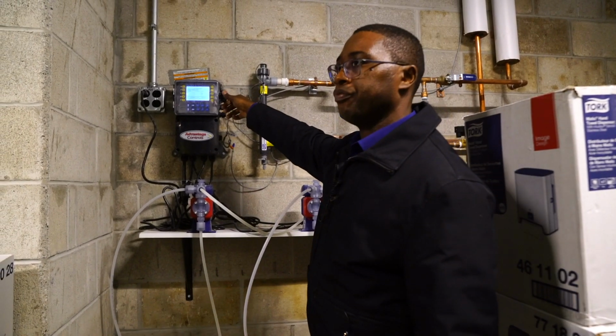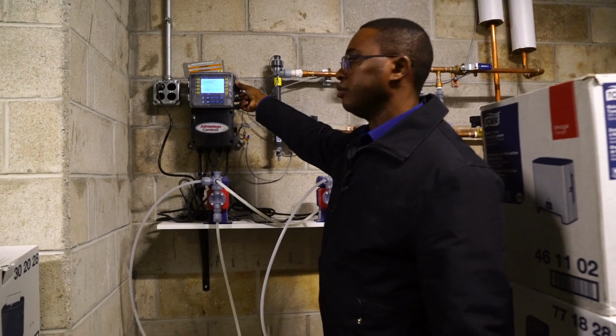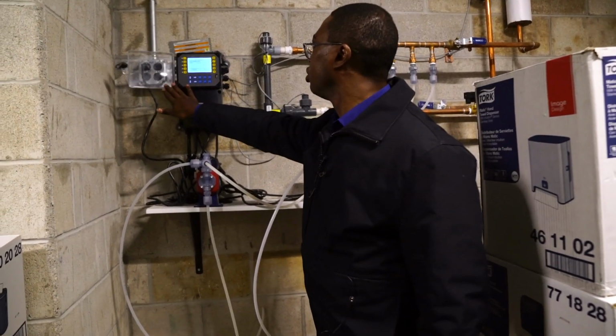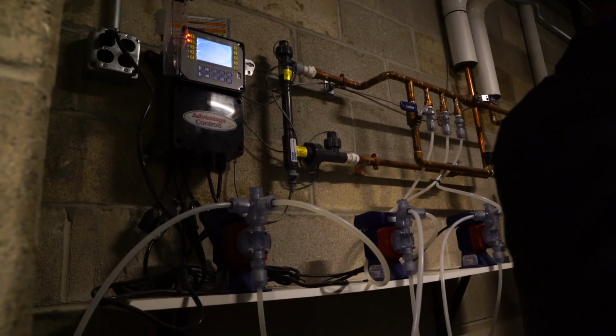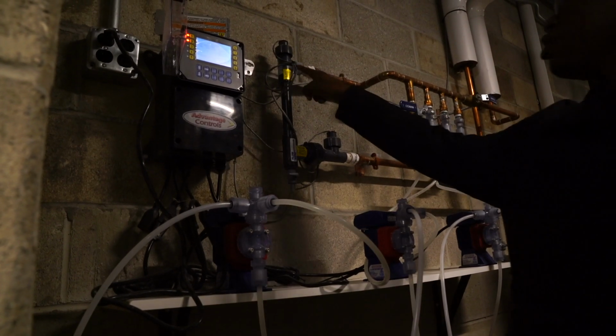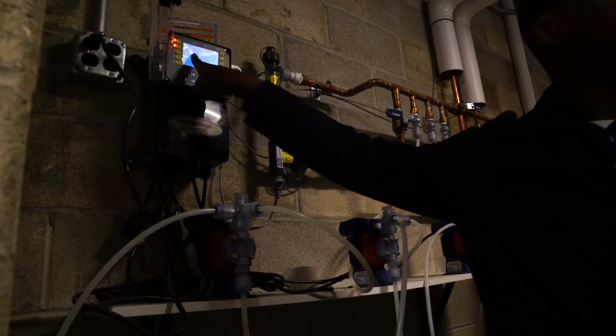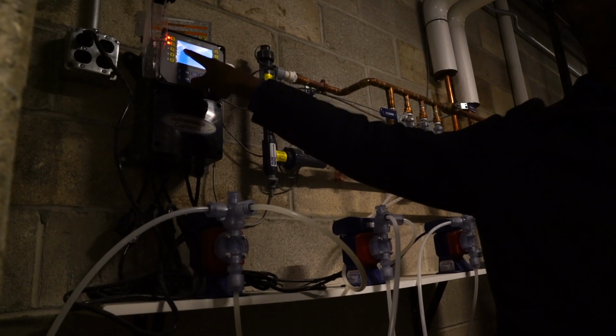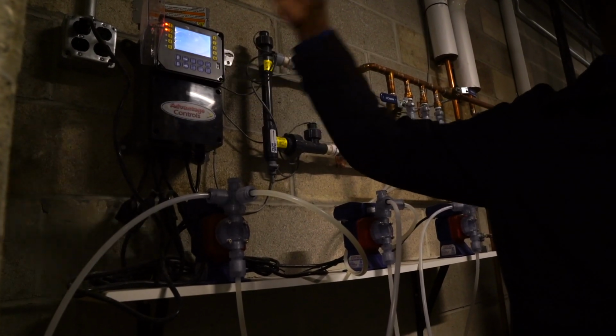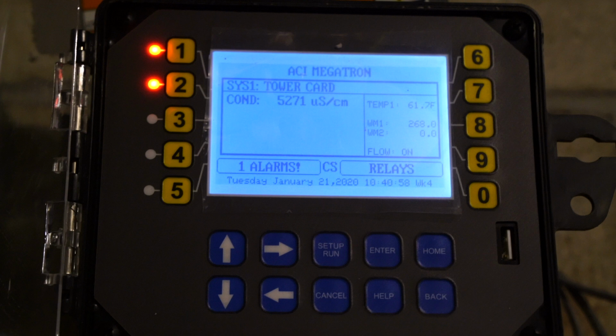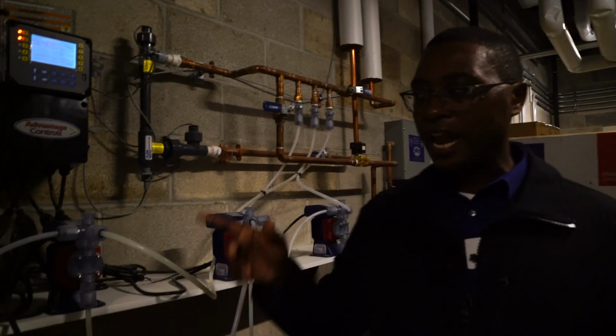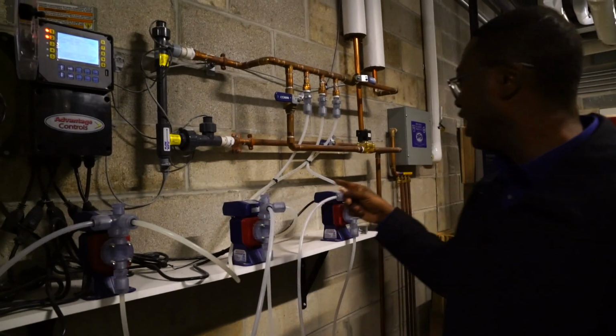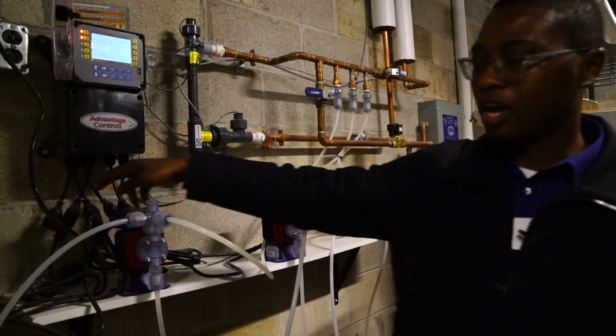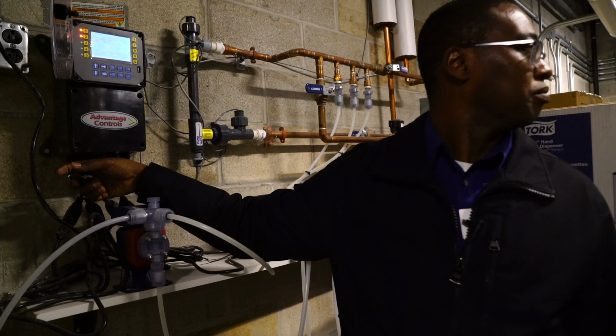Is this module set up currently to be circulating those? Yes, so let's look at it. It's a continuous feed, with a flow sensor. Right now it's reading 5,000. That's 5,000 in TDS, in conductivity. I don't want to see 5,000. My recommendation is that it be at least below 1,500. Now, for it to get to 1,500, I need this thing operating, so I'm going to have to tell Tricon to come and put this on.